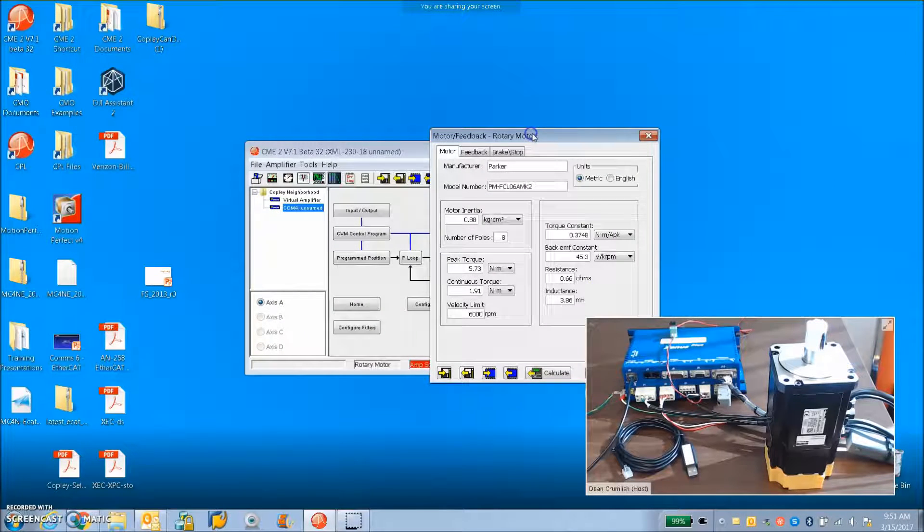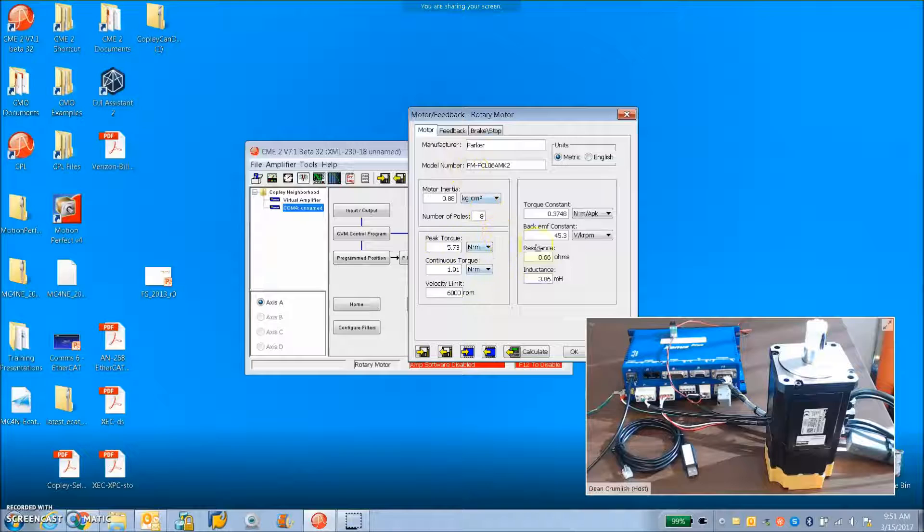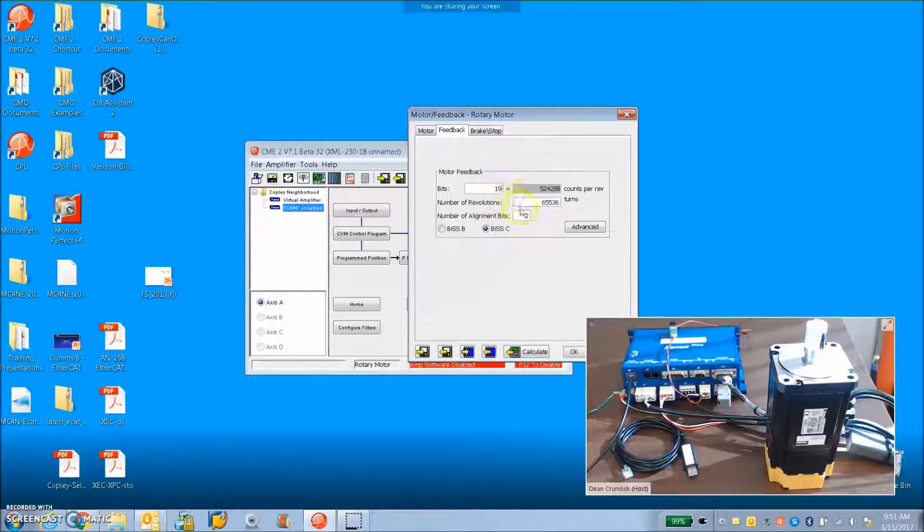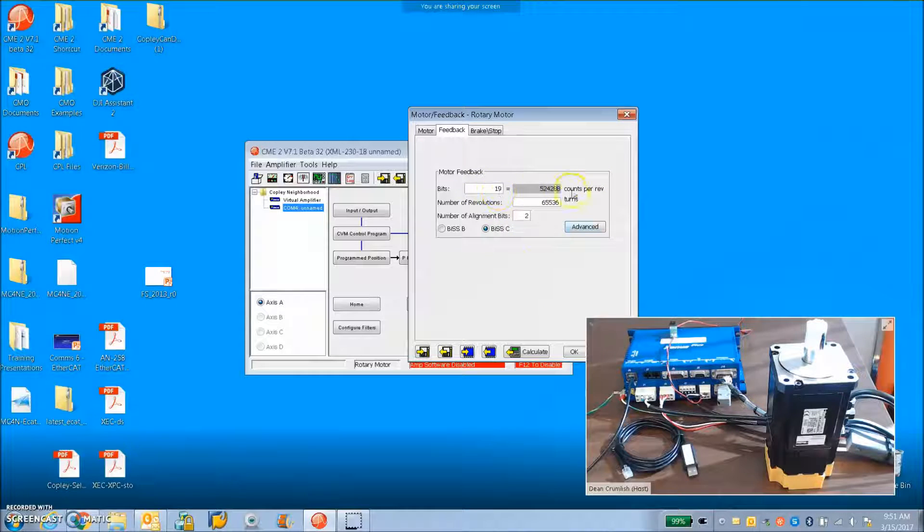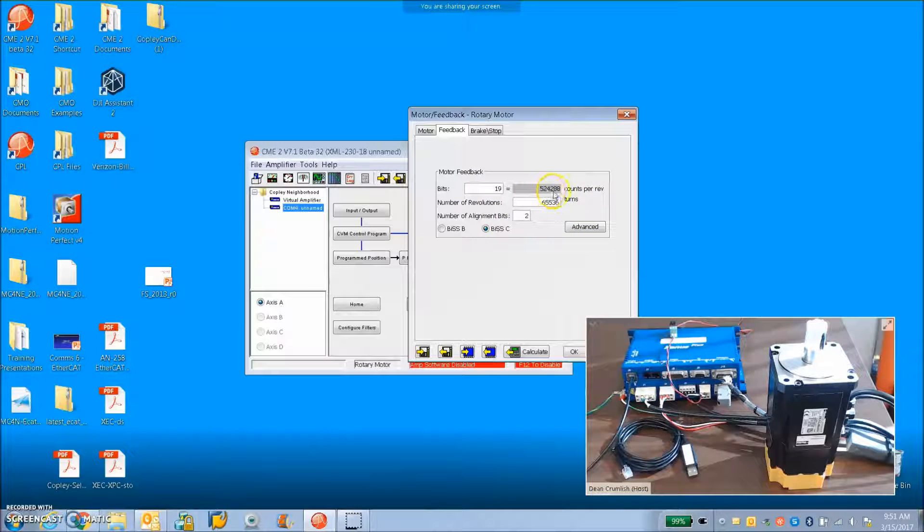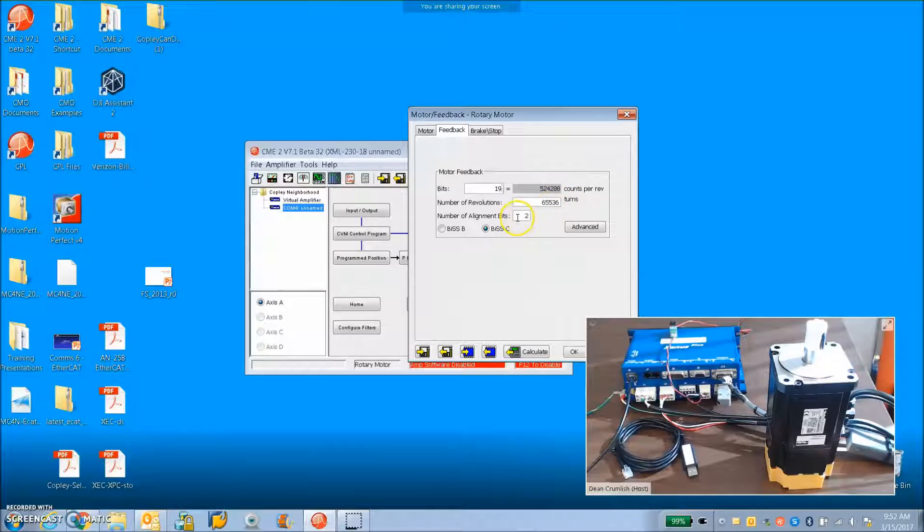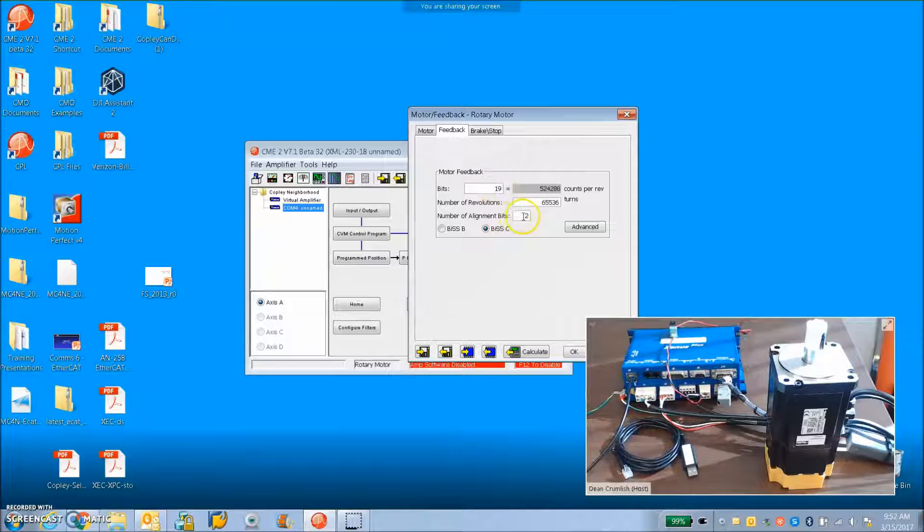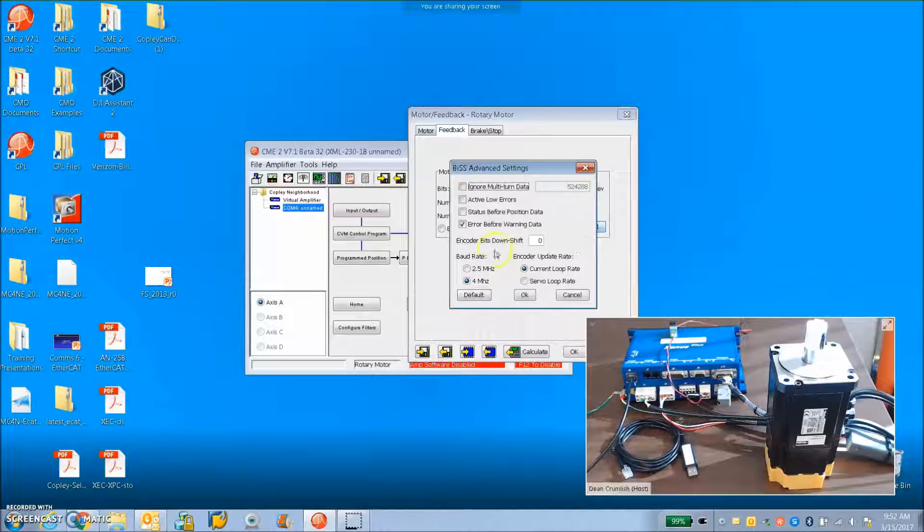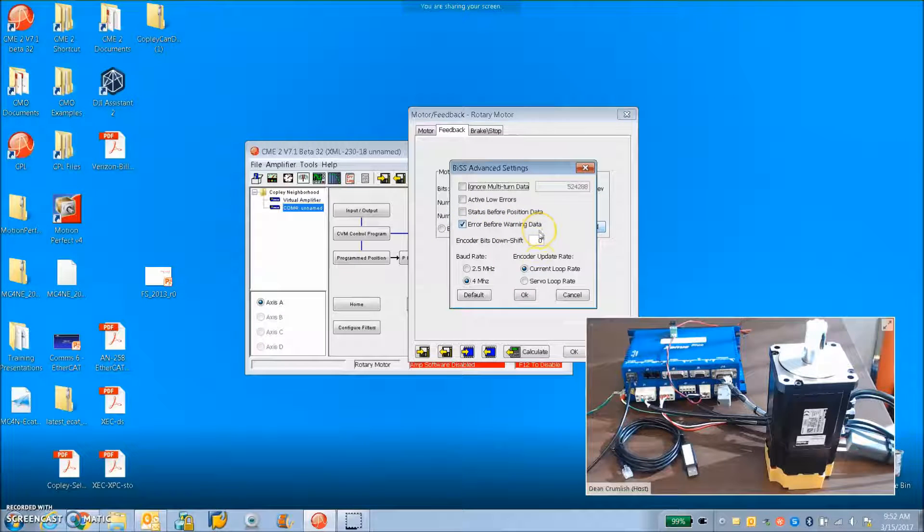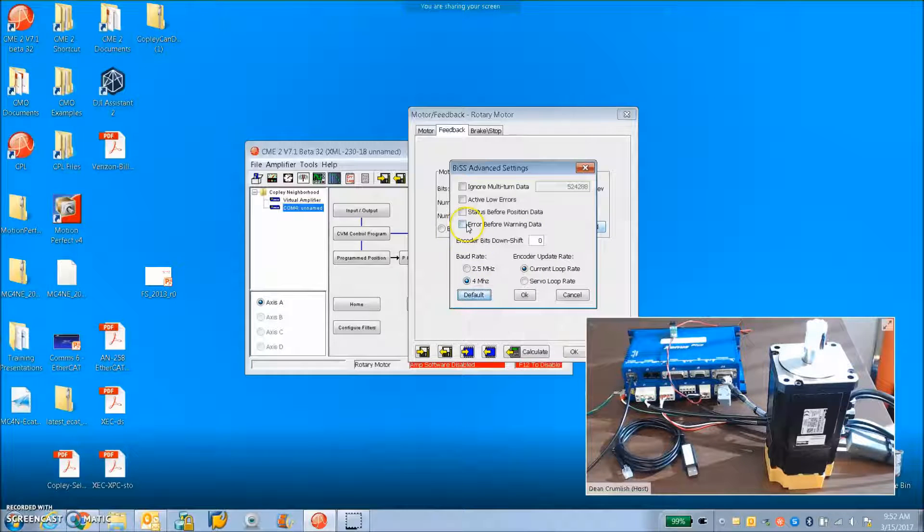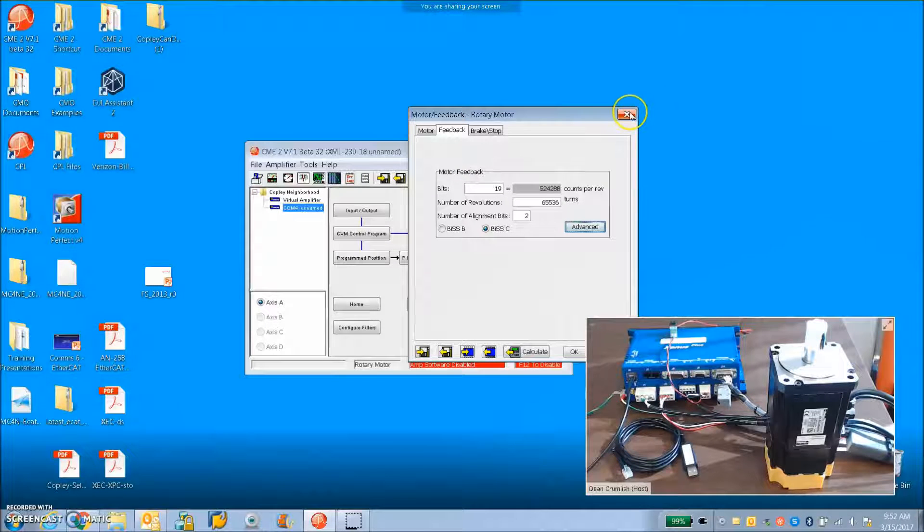On the motor screen we can see I've entered all the data. On the feedback tab, this is the critical factor: it's 19 bits. Even if someone says it's 21, it's really 19 bits. 524,288 counts per rev, 65,536 multi-turn, two alignment bits which means they've given us more bits than 19 and we're supposed to ignore a couple. Maybe that's how they got to 21. In the advanced settings, you can see the error before the warning data and 4 megahertz. If we look at the default, you can see that box is unchecked. So we got to check that box. Now it should work.